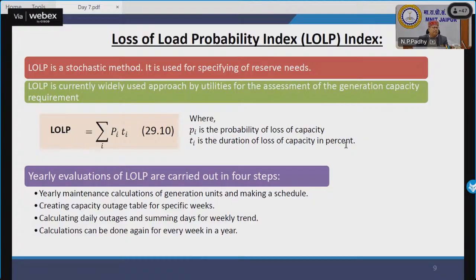Means how much excess energy I must have in my distribution system so that the loss of load probability can be minimized. So LOLP is nothing but summation of PiTi, where Pi is the probability of loss of capacity and Ti is the duration of loss of capacity in percent. Means if I have actually 20 generators to cater my consumers, out of 20, any generator may fail at any given point of time. So I must have excess capacity so that even if someone fails, I must be able to manage.